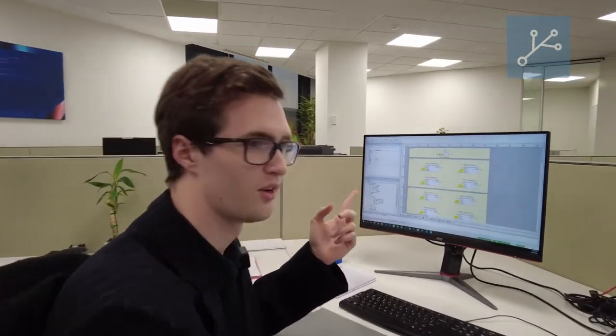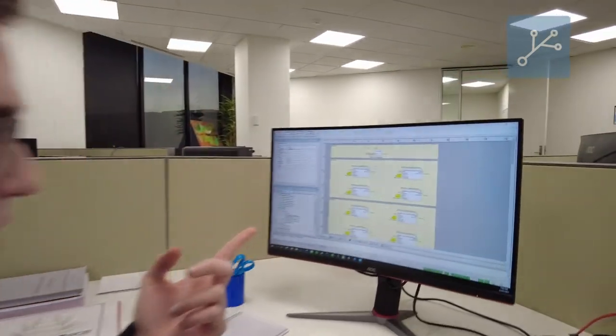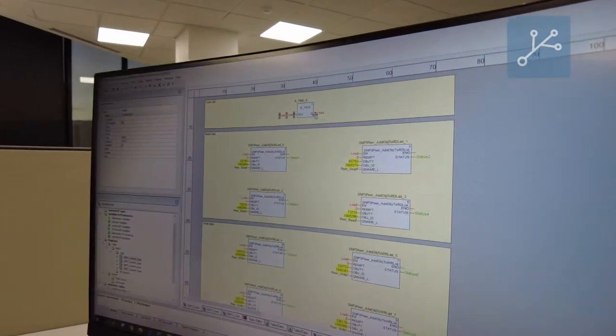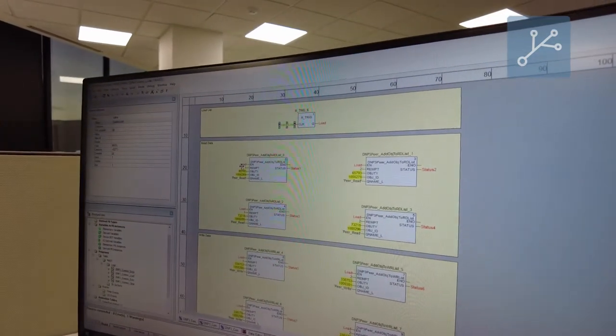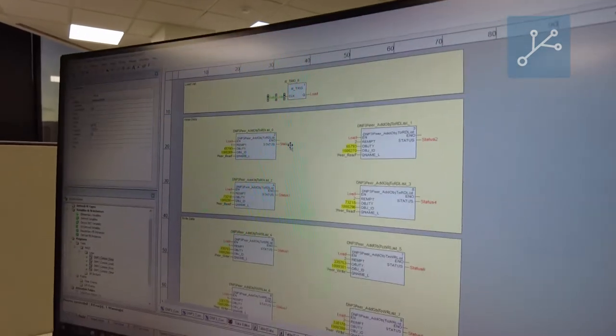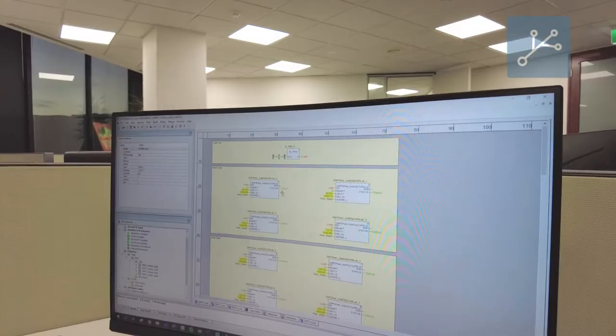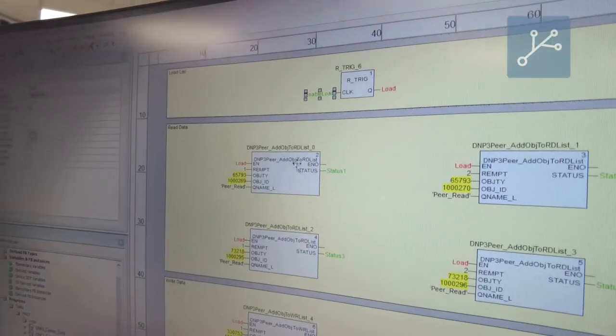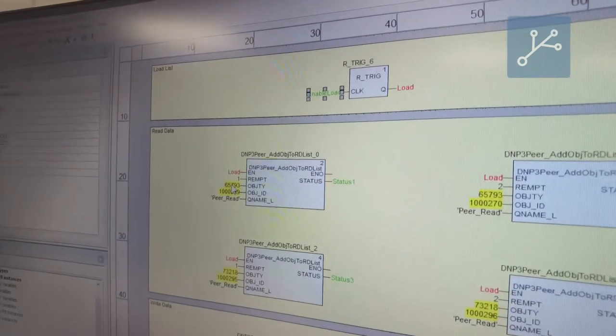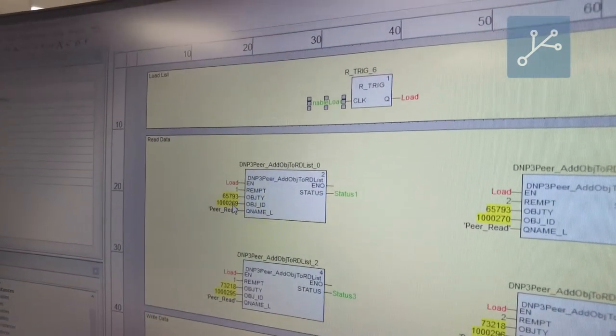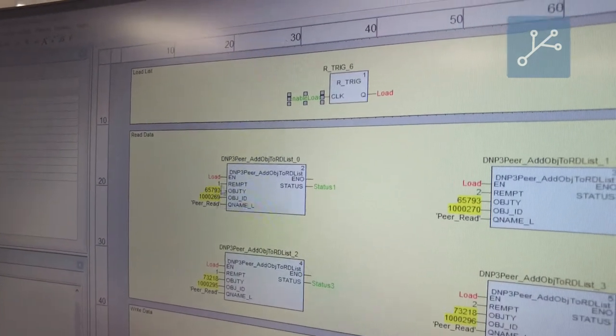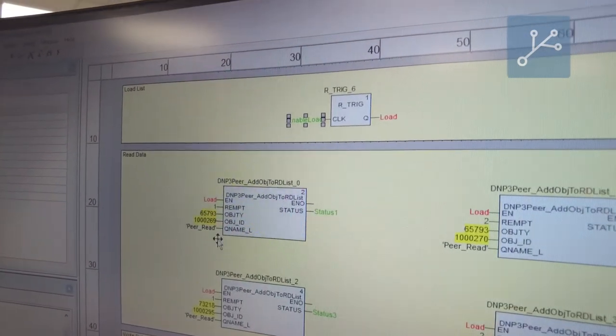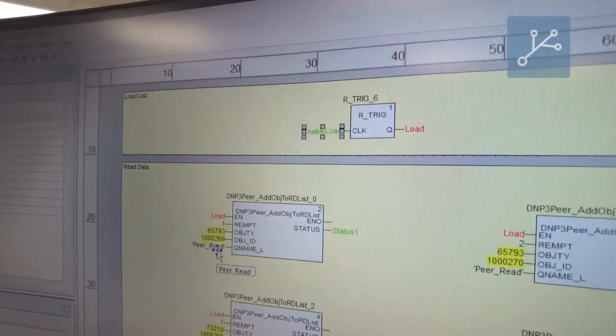Up here I've got a rising trigger block. I set the value to 1 — this will load the configuration in here and this should turn green. We can see that the status is now 1. This has loaded this object ID and this particular point, point 1, into the peer read list.